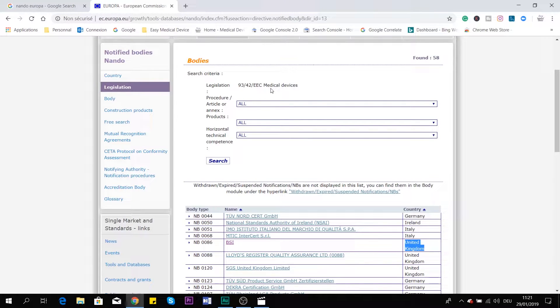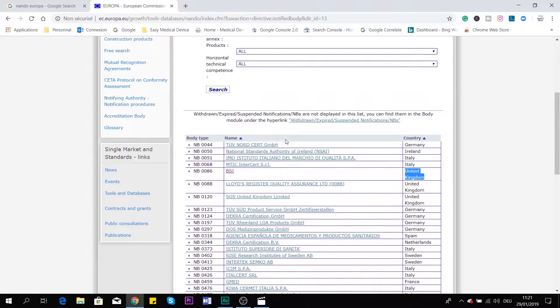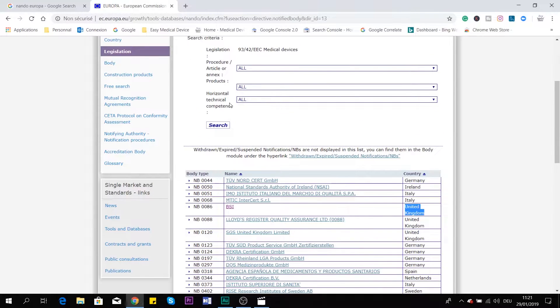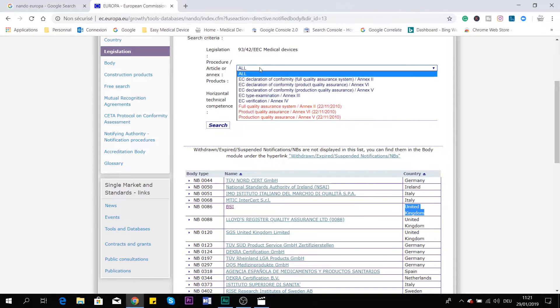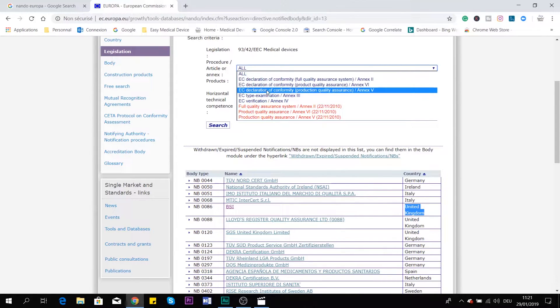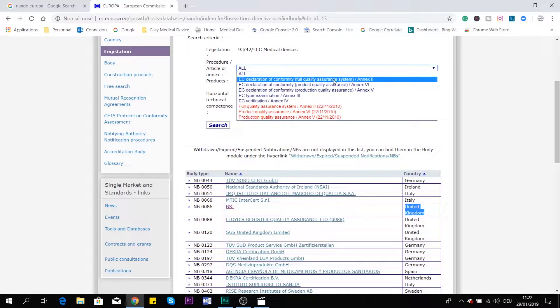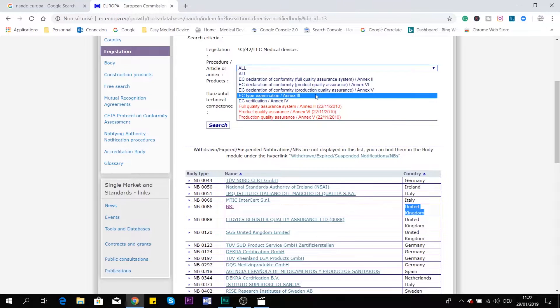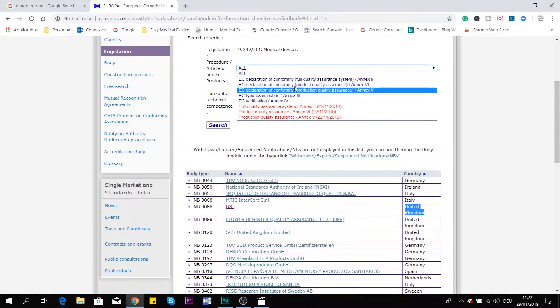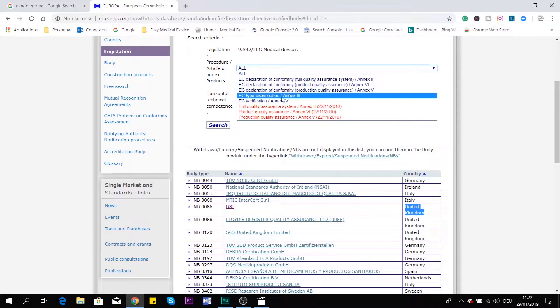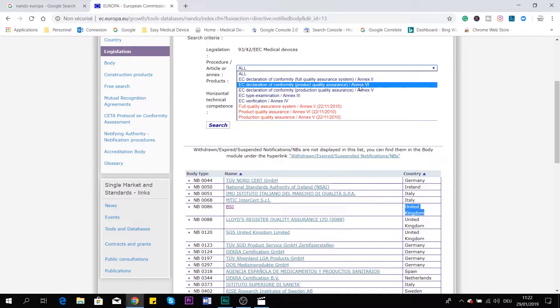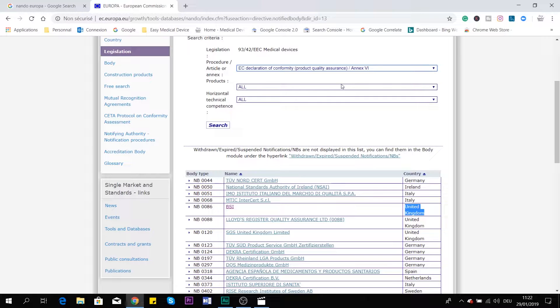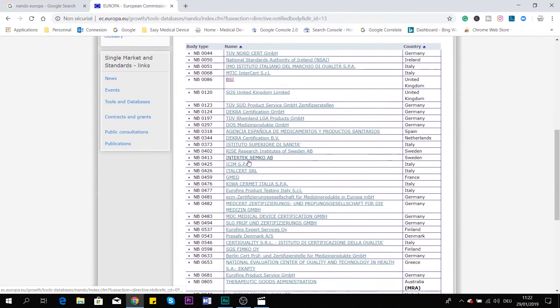If you want to make it more precise, you have filters here. You can decide which conformity assessment you want to go for — for example, a full quality assurance system under Annex 2, product quality assurance under Annex 6, or production quality assurance under Annex 5. So if you decide to go only for product quality assurance, you can filter and see all the notified bodies that are accredited for that specific conformity assessment.